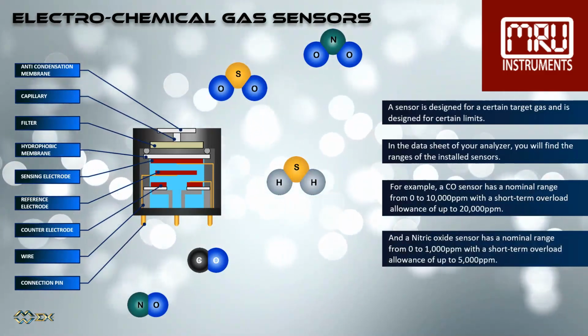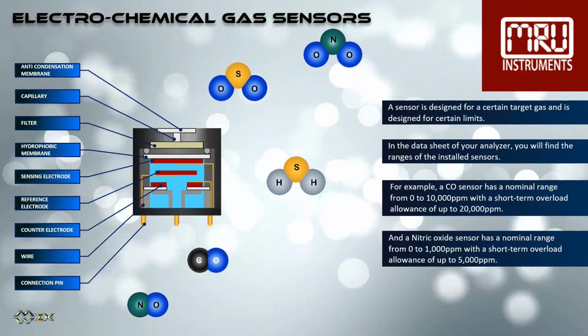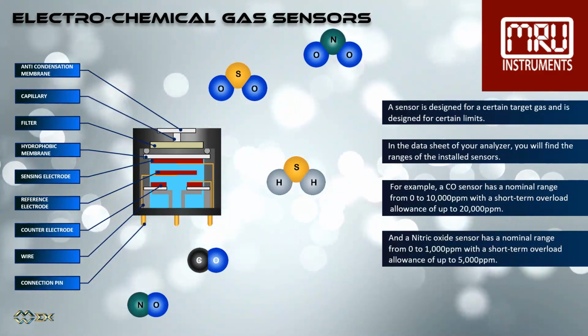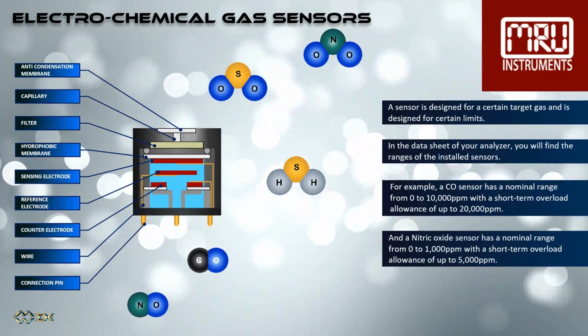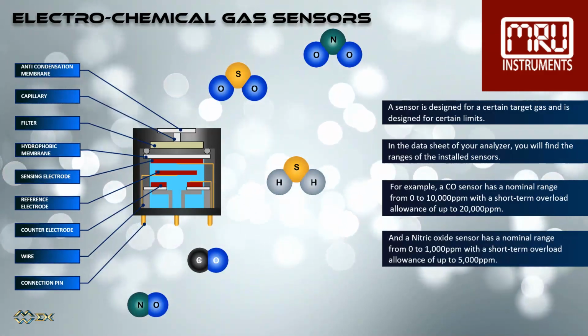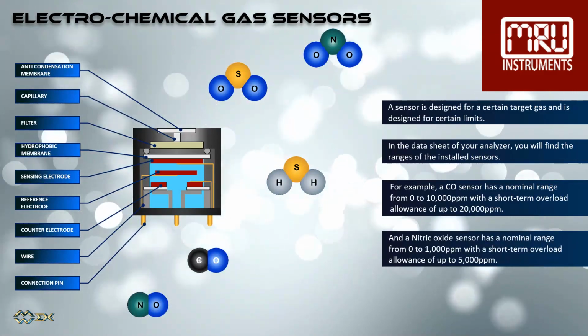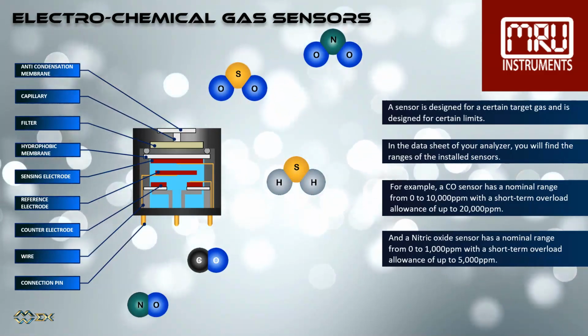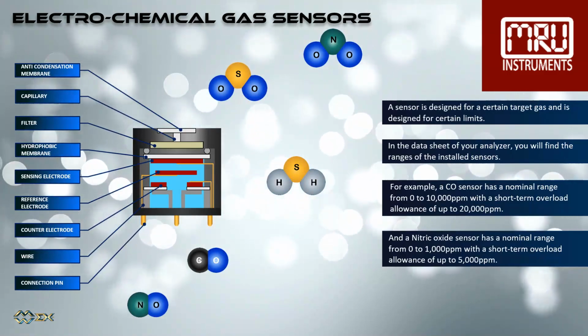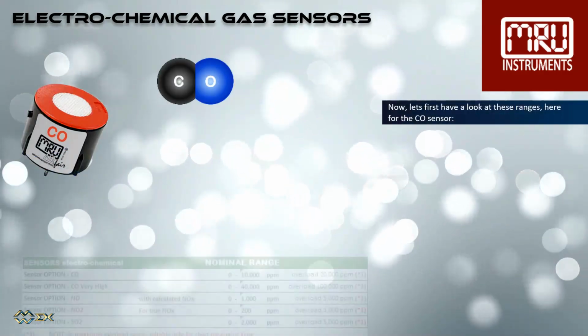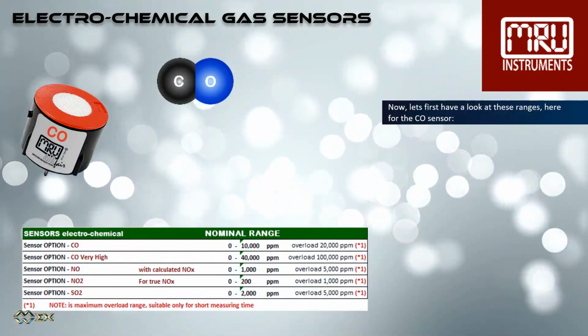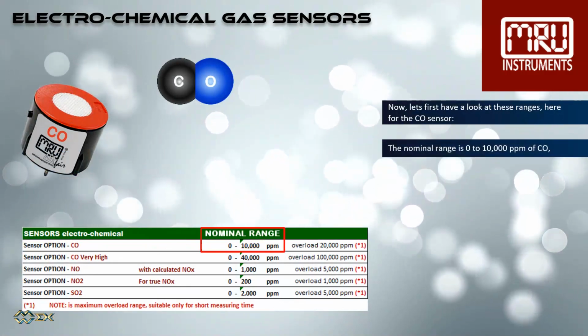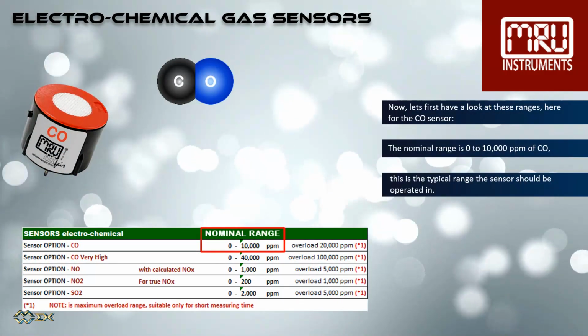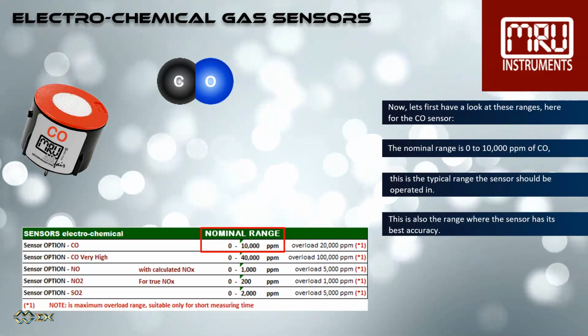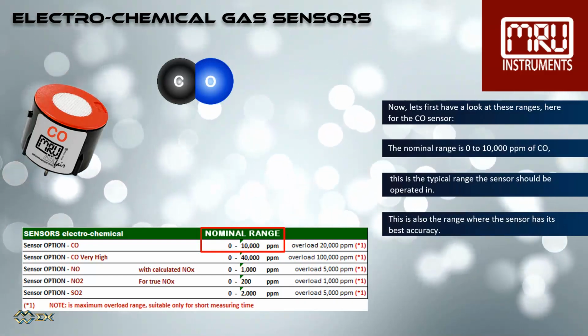For example, a CO sensor has a nominal range from 0 to 10,000 ppm with a short-term overload allowance of up to 20,000 ppm. And a nitric oxide sensor has a nominal range from 0 to 1,000 ppm with a short-term overload allowance of up to 5,000 ppm. Now, let's first have a look at these ranges. Here, for the CO sensor, the nominal range is 0 to 10,000 ppm of CO. This is the typical range the sensor should be operated in. This is also the range where the sensor has its best accuracy.